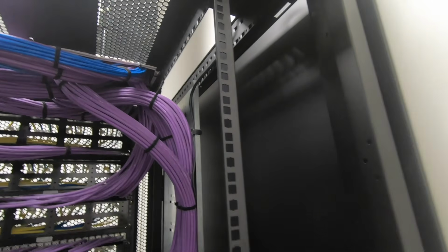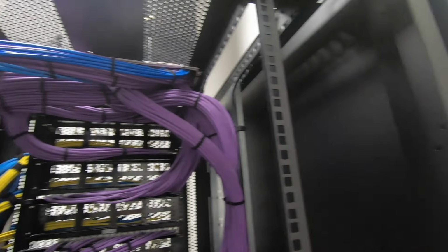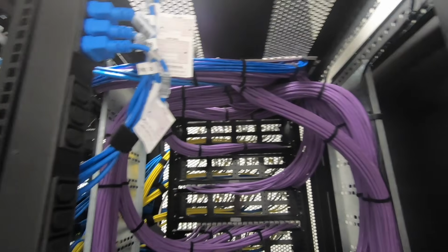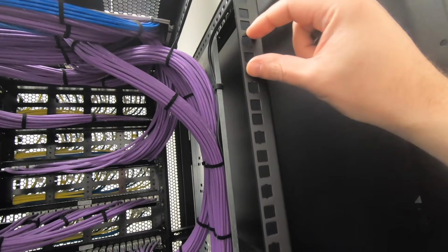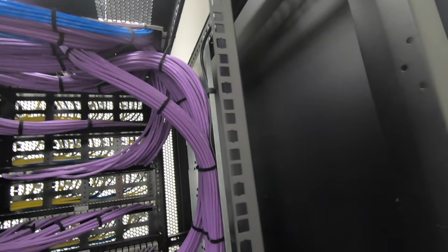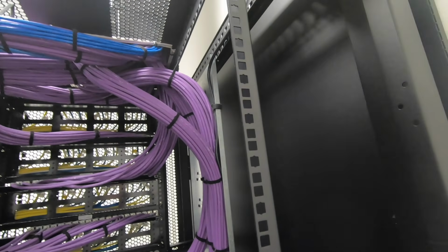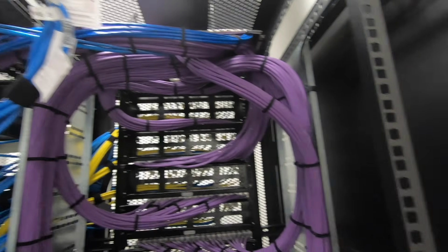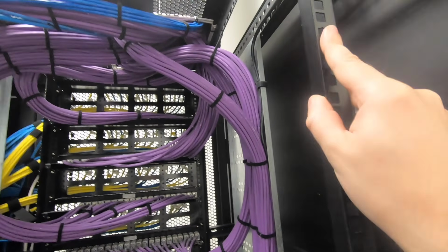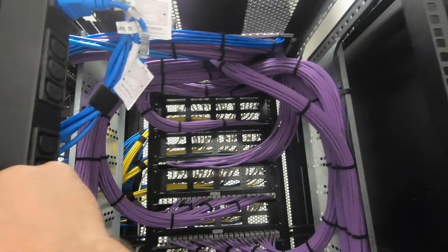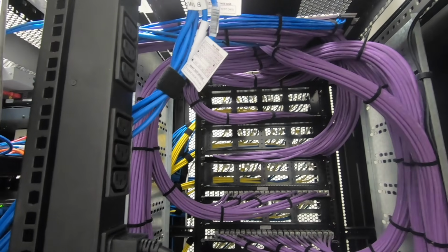Inside of the cabinet, you've got rails on the left and on the right, where you can then go and mount equipment. They're generally grouped into what's called a rack unit. Generally, it's going to be 3 holes, which makes up one RU or one rack unit. And a device that is going to be purchased will be either a 1RU, a 2RU, or 3RU, wherever it may be. And then you put this accordingly to the left and to the right, and you slide that particular device in.